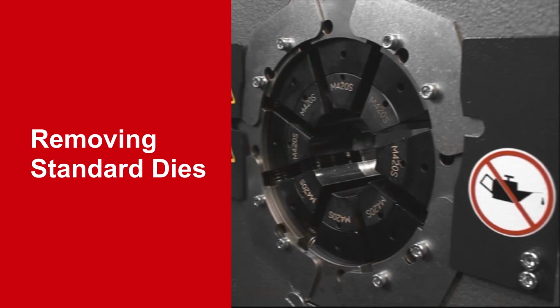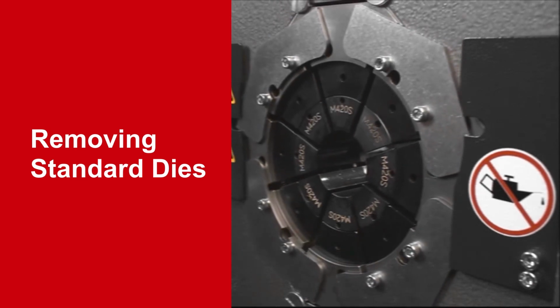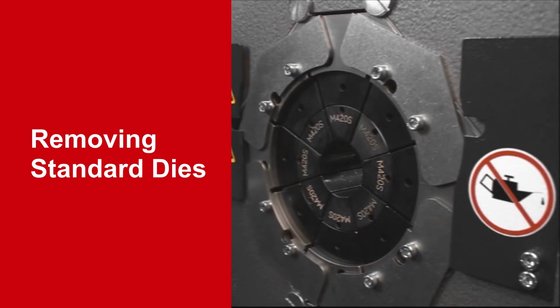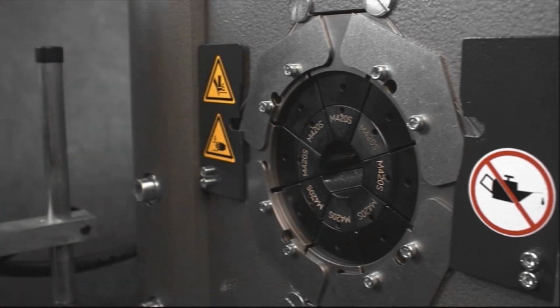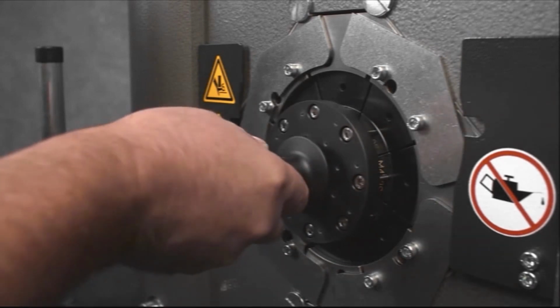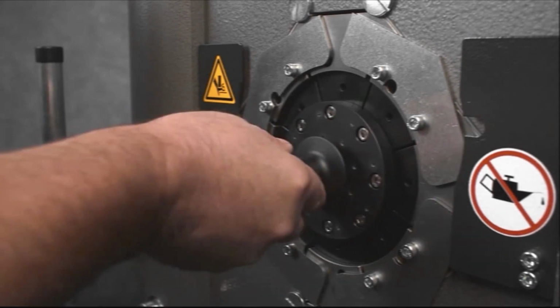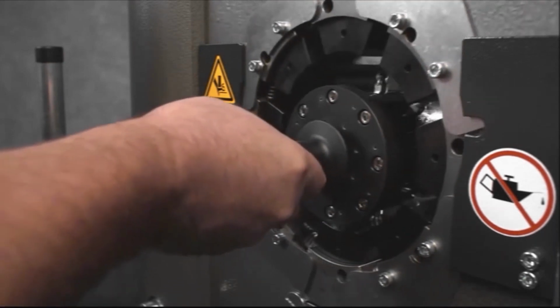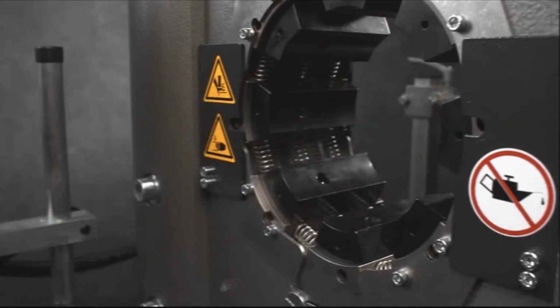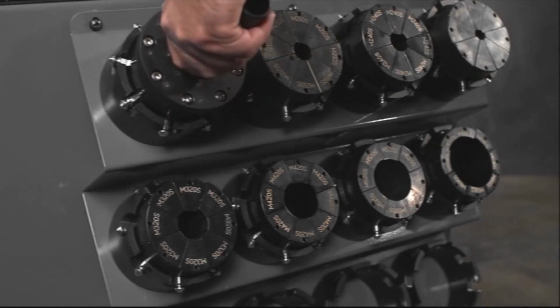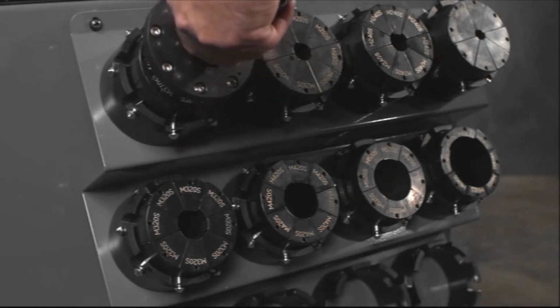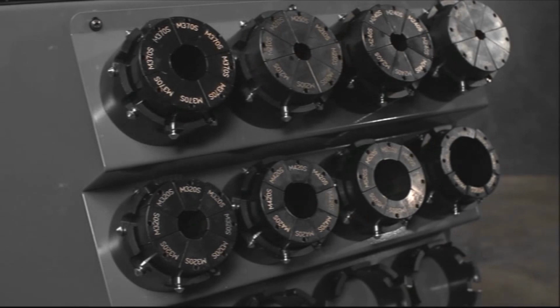To remove the standard bore dies, when prompted to make a tooling change, close the head to the QDC position. The head will stop and the tooling close button will no longer illuminate when in QDC position. Align the 8 pins on the QDC tool with the holes on the crimp dies. Insert the pins fully into the crimp dies until the magnets are fully seated. Gradually retract the crimp head completely until the crimp die holding pins have completely disengaged from the intermediate dies. Place the crimp dies into the storage rack and rotate the QDC to the left, counterclockwise, to lock the die segments into the storage rack.